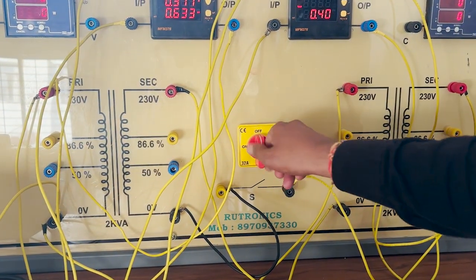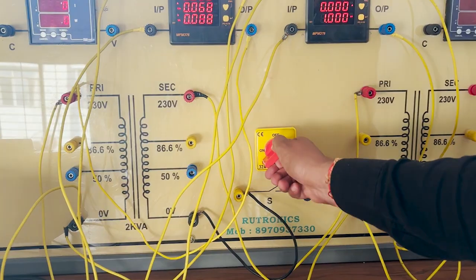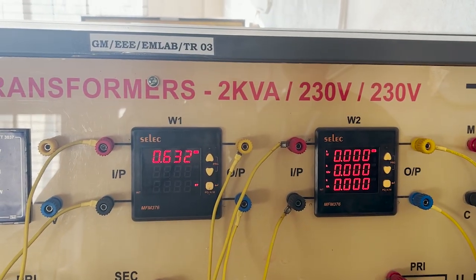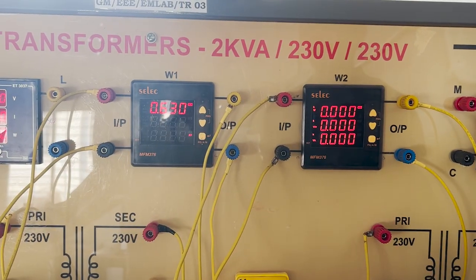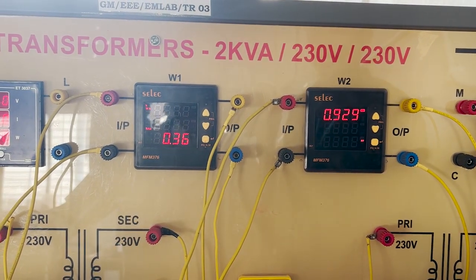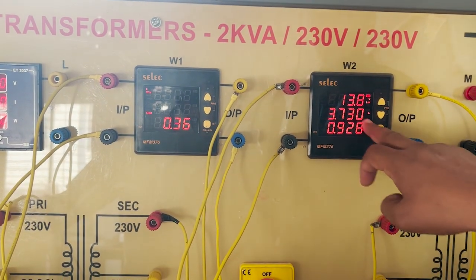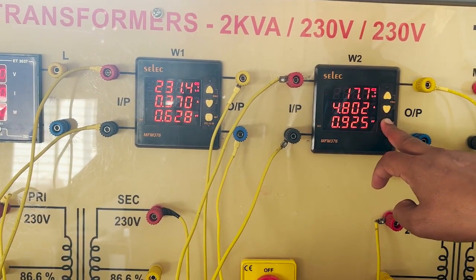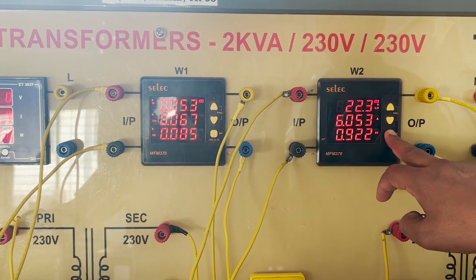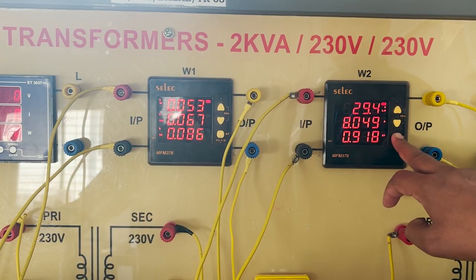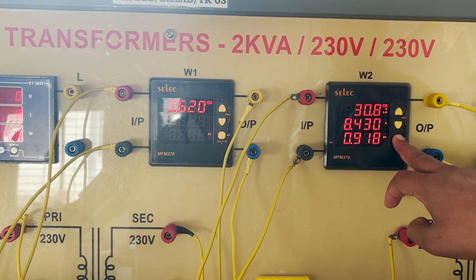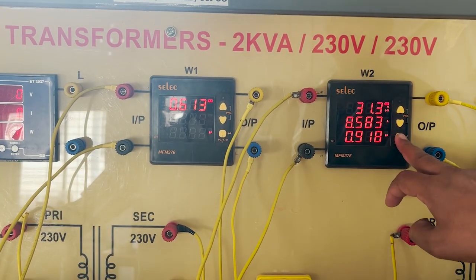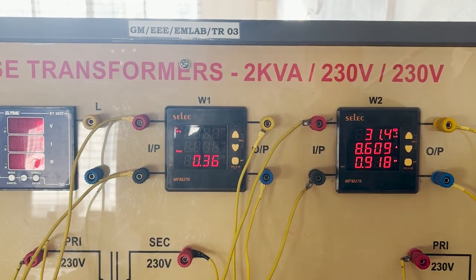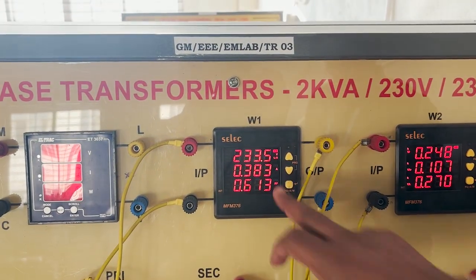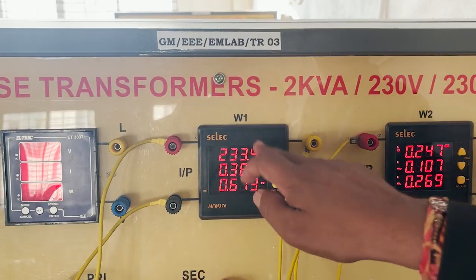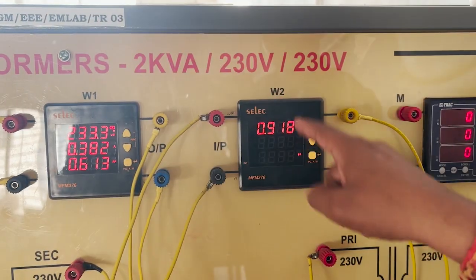Now we have to close the switch from off to on condition. Now vary the auto transformer till it reaches the rated current of the transformer, that is 2 kVA. The rated current I rated is 8.6 ampere. So the current increases 3.7, 4.8, 5.5, 6.0, 7.0, 8.2, 8.4, 8.5, approximately 8.6. Right. Now once we close the switch, you have to take the readings of V1, I1, W1, V2, I2, W2.